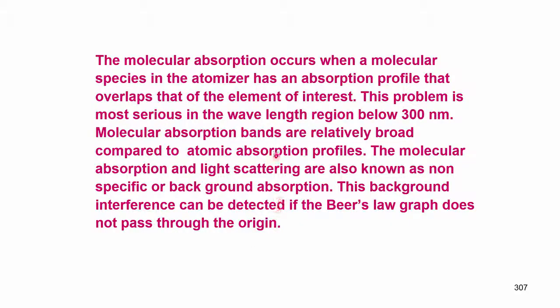Molecular absorption occurs when a molecular species has an absorption profile that overlaps the element of interest. This problem is most serious in the wavelength region below 300 nm. Molecular absorption bands are relatively broad compared to atomic absorption profiles. Molecular absorption and light scattering are also known as non-specific or background absorption.